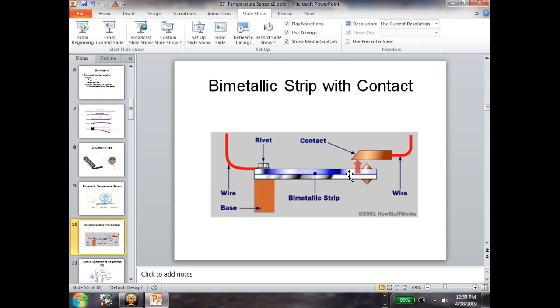Hair dryers use a lot of these. They'll look like a little torpedo in there. If your hair dryer gets too hot or pulls too much current, what'll happen is people won't clean out the thing on the back and it'll start getting clogged up. Then the motor starts bogging down and pulling more current, and then it'll kick out that little thermal strip in there. A lot of motors have this. These are very dangerous because if you overload the motor, it'll kick it out. But what happens when these things cool down? They start back up. So you got to be real careful. Just about all the motors used inside an HVAC system use these little thermal heat overloads inside the motor. Very, very popular.